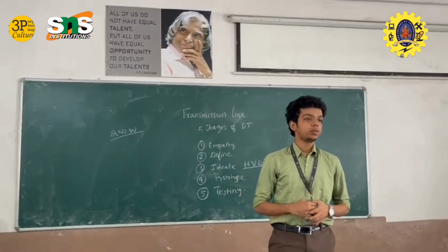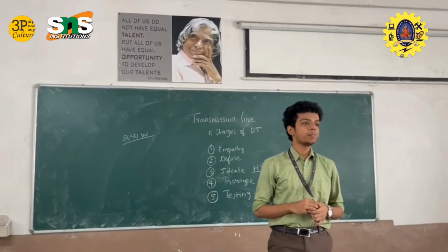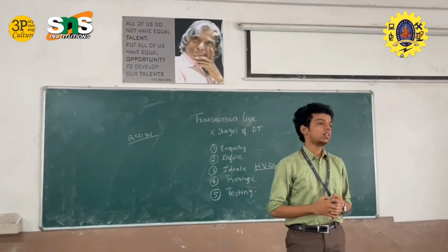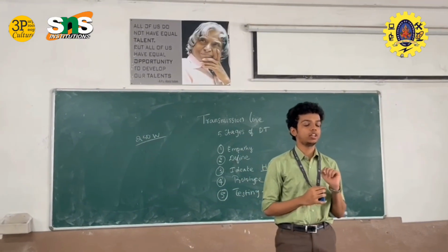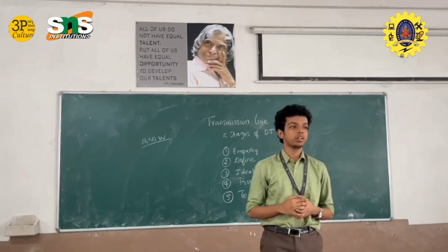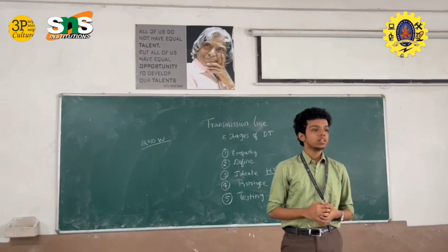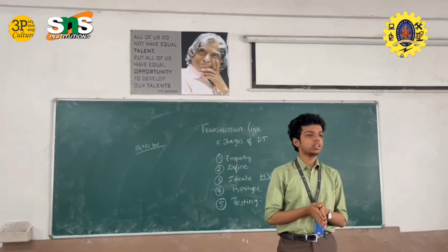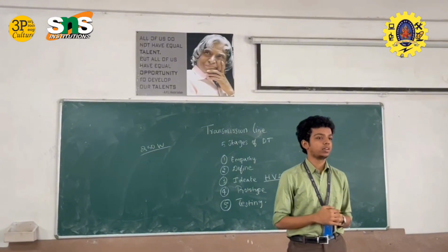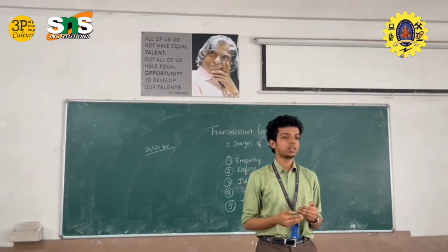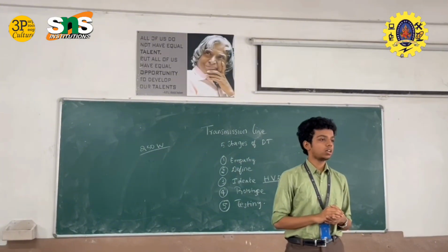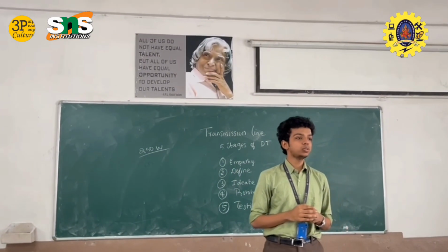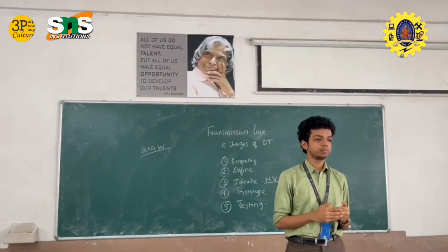Hello everyone, I am going to explain about the testing. For testing, let us compare these transmission lines in different environments like hill station and normal terrain regions. In hill station, due to higher altitude and unstable air density, the dielectric strength of air decreases, leading to a reduction in corona threshold voltage. So this leads to high corona loss, audible noise and electromagnetic interference.